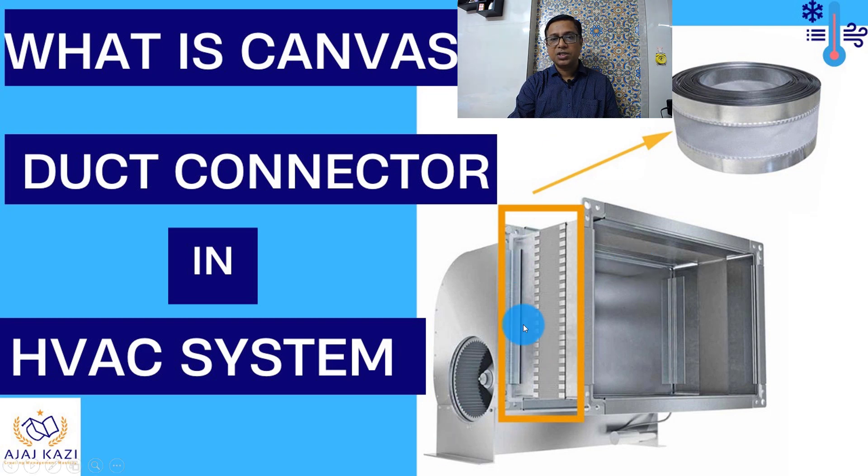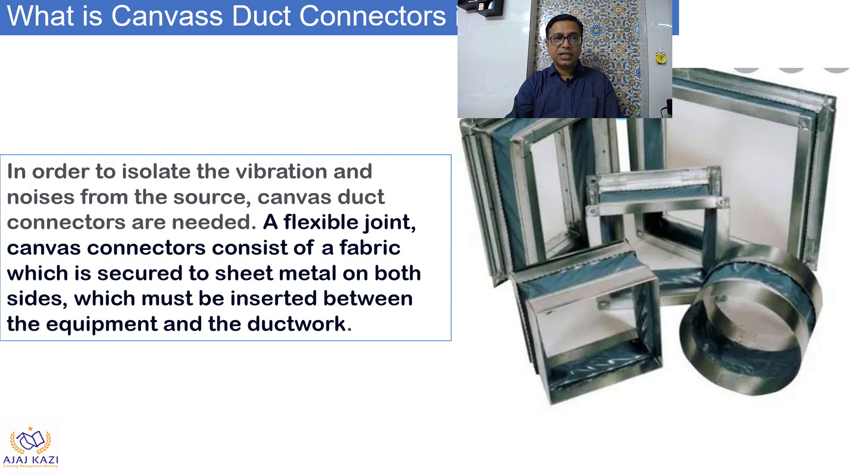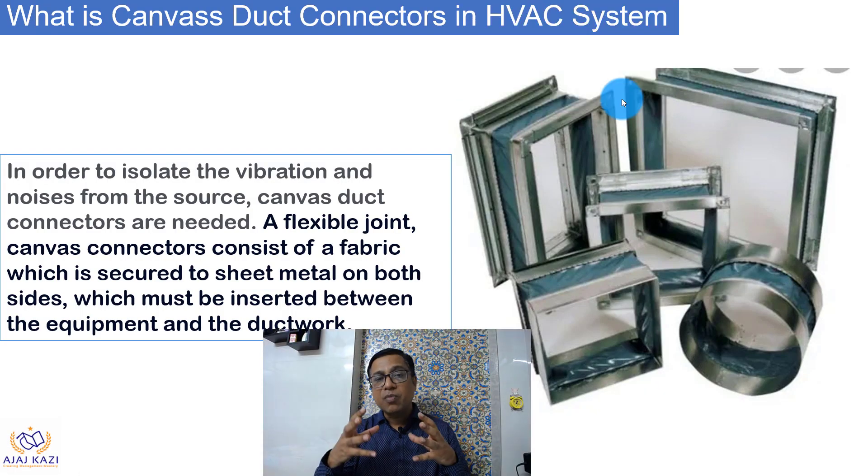You can see the pictures over here. This is the duct connector, or canvas connector, which is used for various connections of equipment. In order to isolate or minimize the vibration and noise from the source — the equipment — flexible joint or flexible duct connectors are used. This fabric is connected to sheet metal on the both side, which connects to equipment on one side, and ducts on the other.